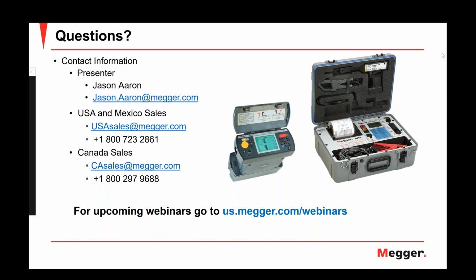All right, thank you. Sanket, how long does it take to get a stable impedance reading on the BITE 2P and BITE 3? The time differs for each measurement, and one of the reasons is the way the test is done. When you test with the BITE 2, you are injecting the current continuously throughout the string, and you take voltage measurements across each cell.